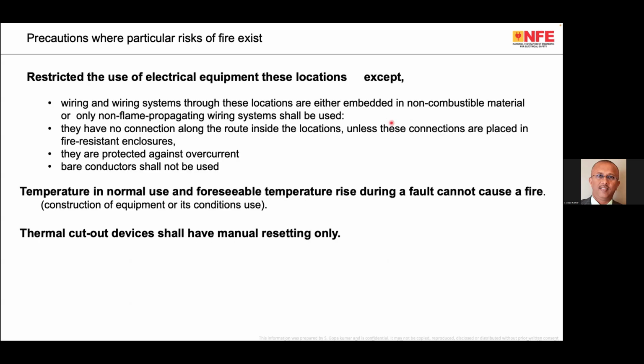Now, with respect to fire, for example, in locations where a particular risk of fire exists, the amount of electrical equipment used in that particular area has to be restricted. Don't try to put so many electrical apparatus in this particular area, because there is already a chance of fire. If the wiring is passing through this particular area, you have to take care that the wiring and wiring systems through these locations are either embedded in non-combustible material. Only non-flame propagating wiring systems shall be used. They have no connection along the route inside the location. That means no joints in this location unless these connections are placed inside flame retardant, flame resistant enclosure. They are protected against overcurrent. Bare conductors shall not be used.